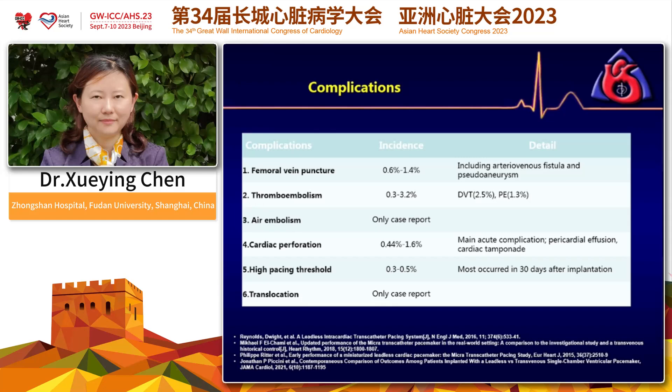Similarly to conventional pacemakers, high pacing threshold may require a generator change. For Micra, the incidence is around 0.5%, and it most often occurs in the 30 days after implantation. Other very rare complications include air embolism and translocation — there are only some case reports, so these are not very common.